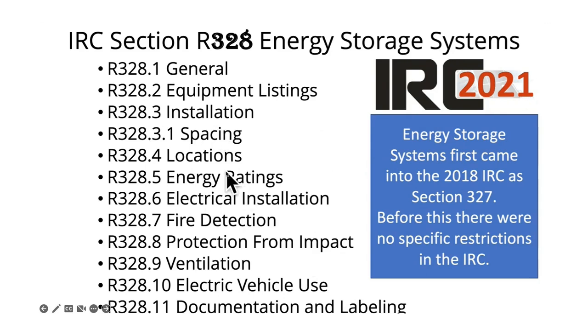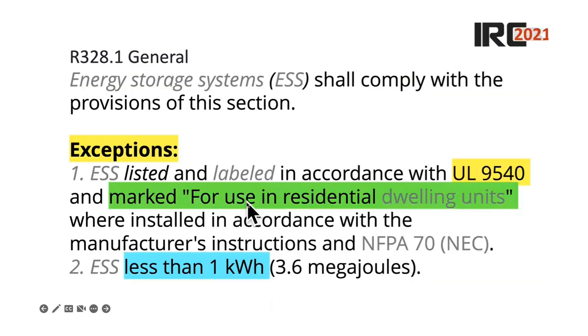And in between here, I'm going to go off because the IRC points to the IFC, and then I have just about as many slides for the IFC as I do for the IRC here. So we got to comply with 9540, and if it's going to be residential, also energy storage shall comply with the provisions of this section, with the exception of, so if something is 9540 and marked for use in residential dwelling units, then you actually kind of don't have to follow even the IRC and all this stuff that we're talking about, which is kind of interesting. And then also you don't have to follow it with less than 1 kilowatt hour, same as what it says in the NEC. And also this one too, where it says if it's marked for use in residential dwelling units, you still have to follow the manufacturer's instructions and NFPA 70, that's the NEC.